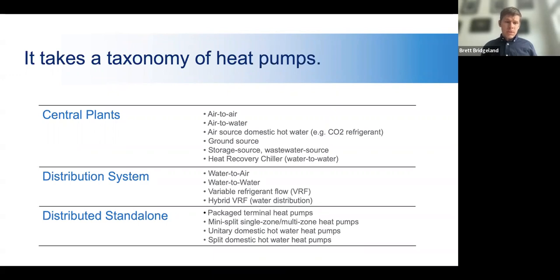There are also types of heat pumps that sit in the building distribution systems, extracting heat from a hydronic loop and putting it into space, or water to water, or VRF (variable refrigerant flow), or hybrid VRF, which rather than running refrigerant around in space, runs water for the distribution. And then, of course, there are distributed standalone types of heat pumps: package terminal heat pumps through the wall, mini split systems, and equivalents on domestic hot water.